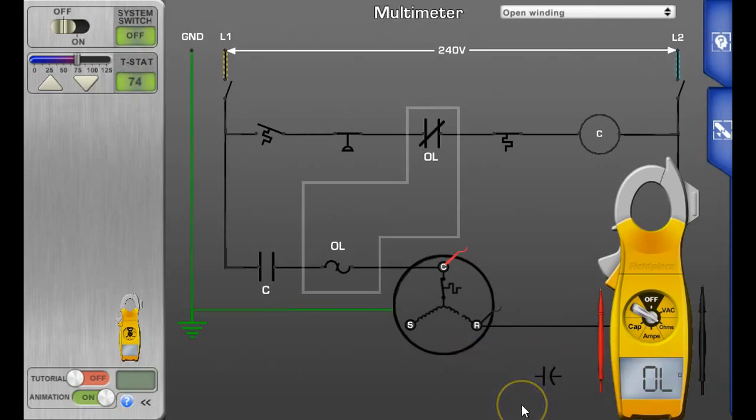That means the winding is possibly open, but the one thing you can't rush into is—let me draw it on here for you—we have the internal overload. If the compressor has overheated, that internal overload is going to open up and you're going to measure infinite resistance or an overload on your meter.